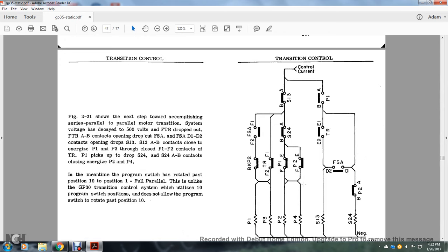Alright, it shows the next step in accomplishing the series-parallel motor transition. System voltage decays with the 500 volt, the front transition relay drops, the front transition relay AB contacts open, the front transition auxiliary D1 and D2 contacts open, the S13 drops, S13 AB contacts open, and the energized P1 and P3 close. F1 and F2 contacts, TR and the transition relay pick up, the P1 contacts drop, and the S24 A and B contacts close, energizing P2 and P4.